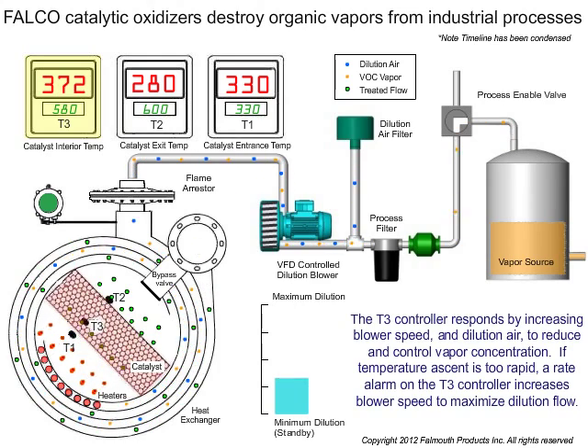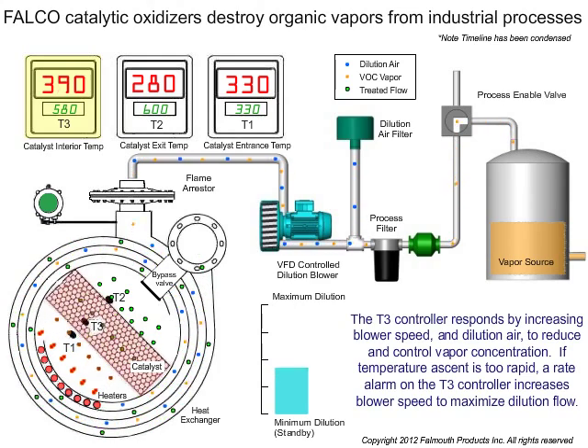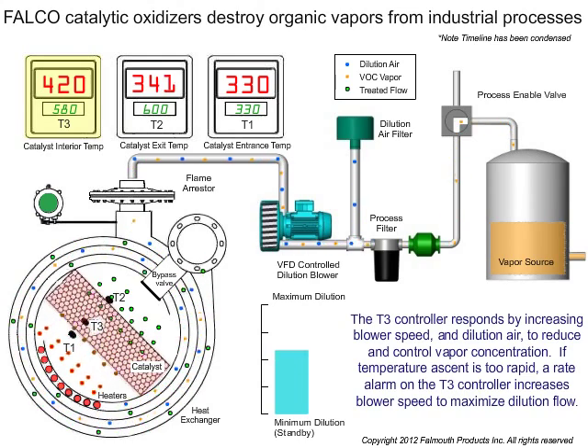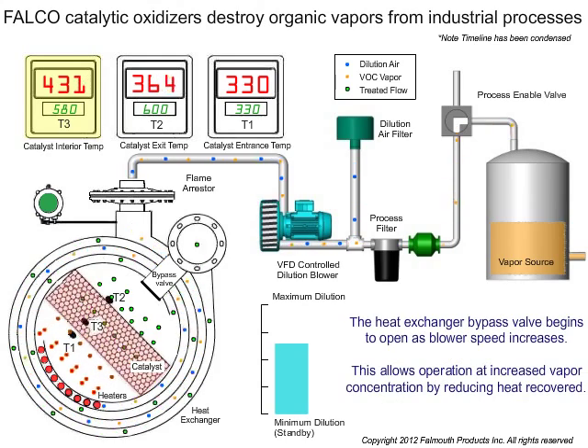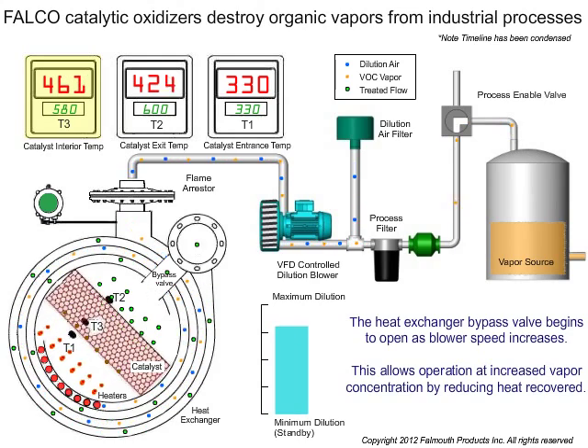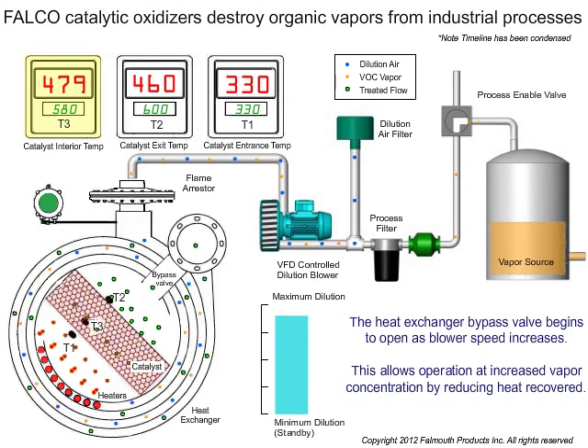If temperature ascent is too rapid, a rate alarm on the T3 controller increases blower speed to maximize dilution flow. The heat exchanger bypass valve begins to open as blower speed increases, allowing operation at increased vapor concentration by reducing heat recovered.